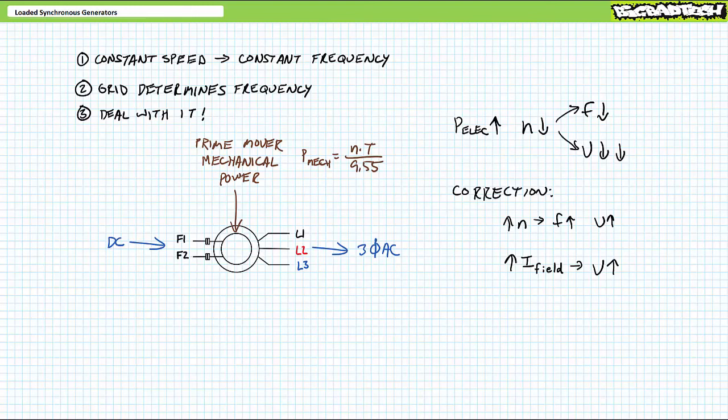Now, consider what happens to this generator when this high-demand electrical load suddenly disconnects. In this doubly compensated state, the prime mover would suddenly speed up given a sudden loss of oppositional torque, and both frequency and voltage magnitude would spike because of the increased rotational speed and high field current. In order to prevent damage to the generation facility and the electrical grid, an operator would need to quickly slow the prime mover and decrease field current. This is again to suggest that monitoring and maintaining a stable grid is not without its challenges and complications.